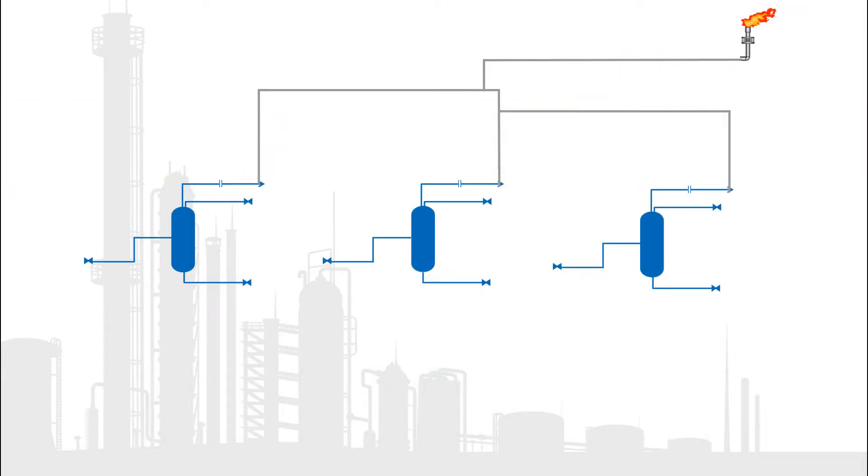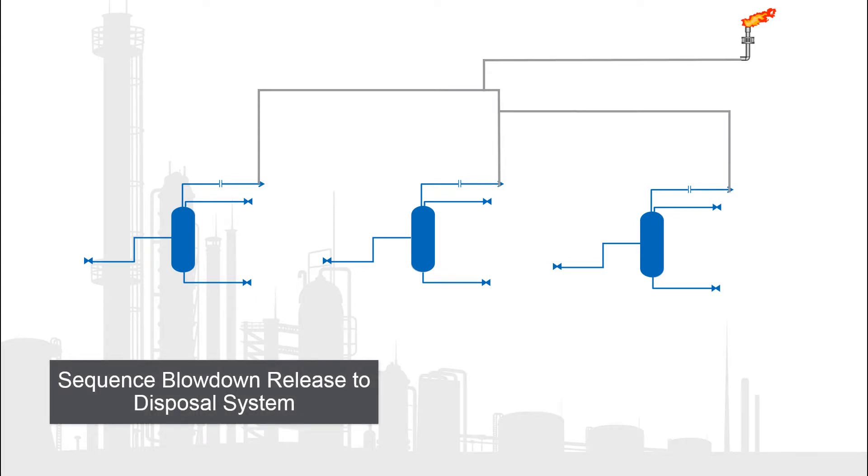A staggered blowdown system, where blowdown valves are opened in a predetermined sequence, is an excellent way to keep the peak flow at the flare header below the threshold while still discharging in the required time.